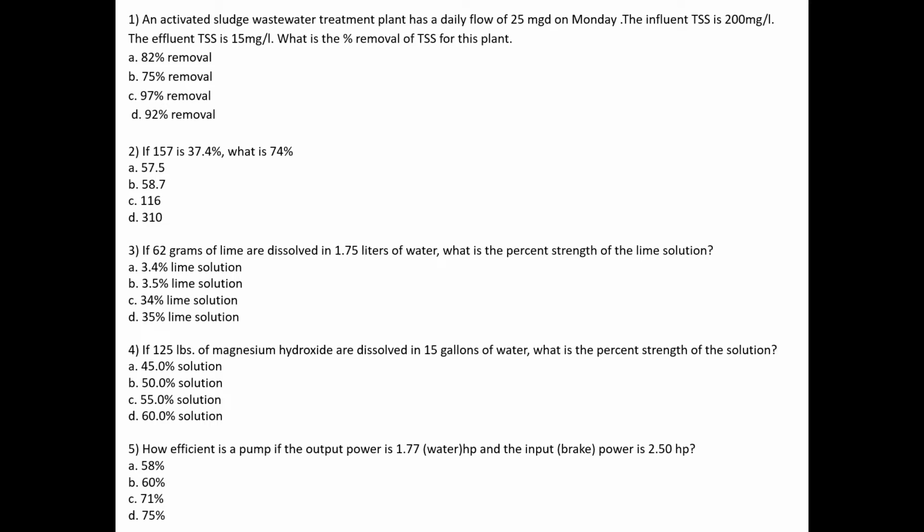And the purpose of this is to add alkalinity to the water, usually to adjust the pH, to maintain that. Because you add a little bit more. Now, it's only 1 liter of water, so this is making a solution that you're going to be adding to the bigger picture, so to speak. So for every 62 grams of lime, you use 1.75 liters of water to what they call flake it. You mix the water and you make it like a cake dough.